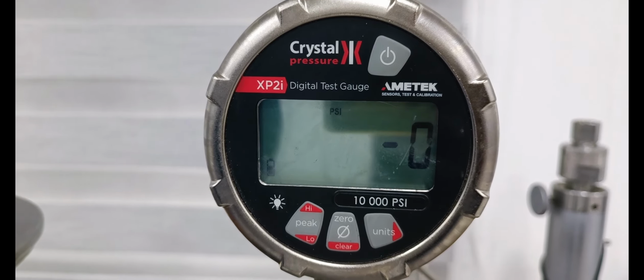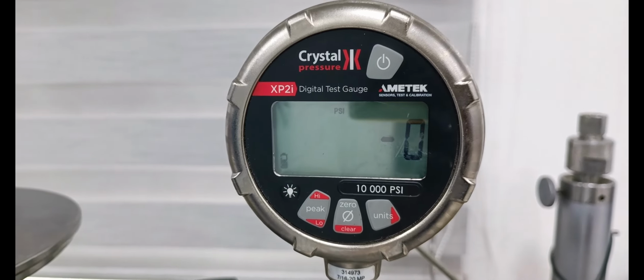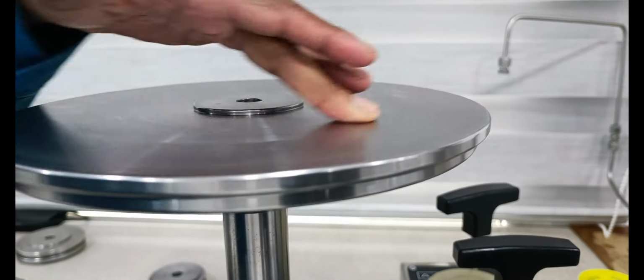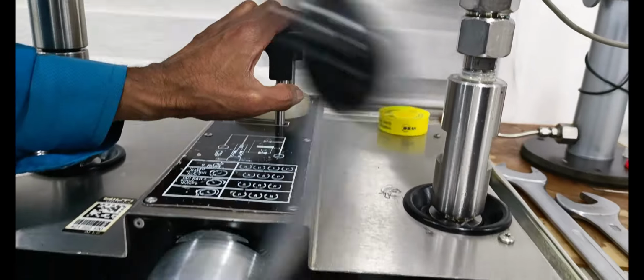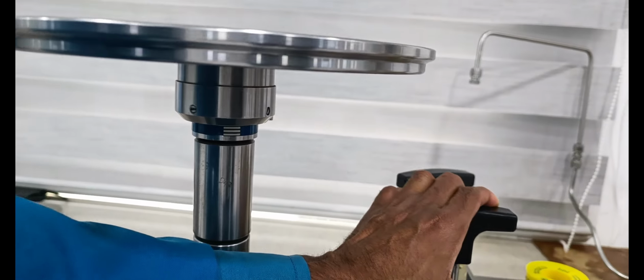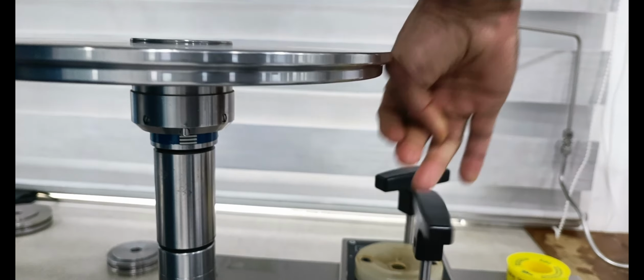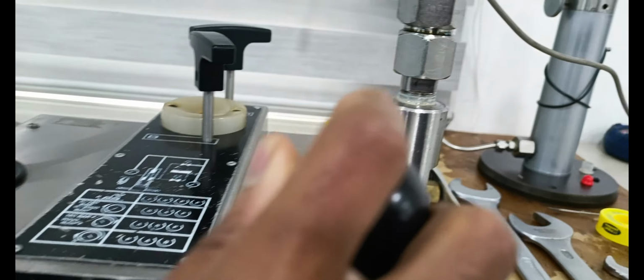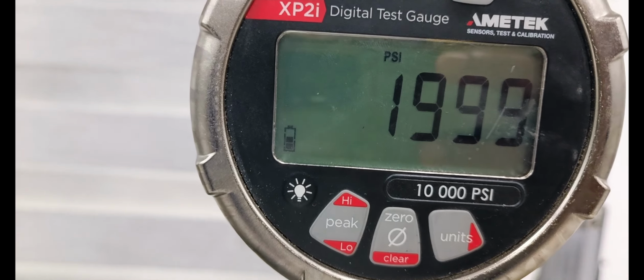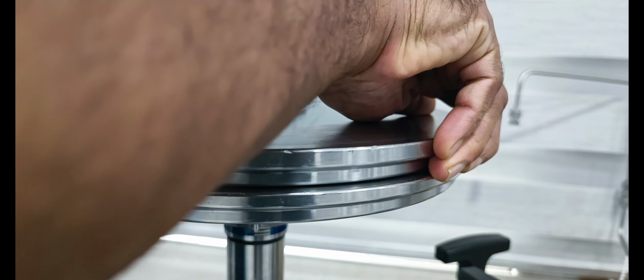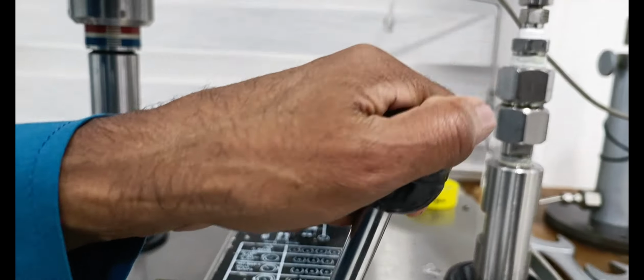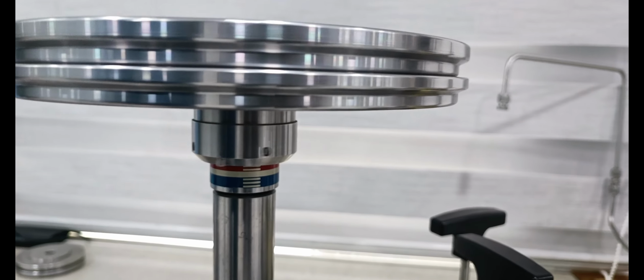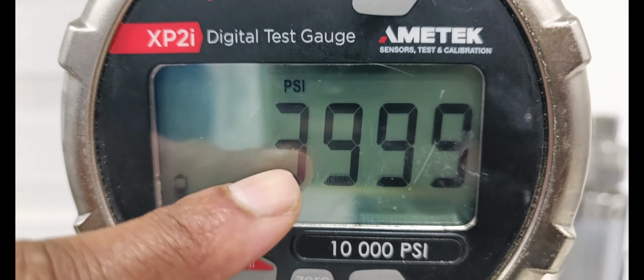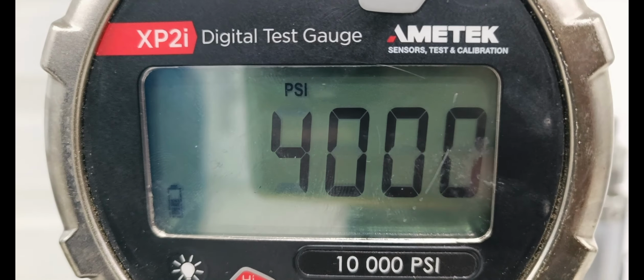Next, we are checking the 5-point reading verification. Now we apply 2000 psi and generate the pressure. Now 2000 psi is applied. The display is showing 1999 psi. Next, we insert more weight. Now the total weight is 4000 psi. It is showing 3999 psi. 6000 psi.